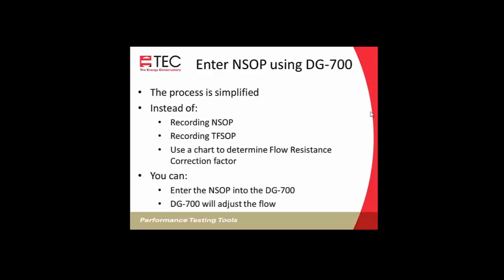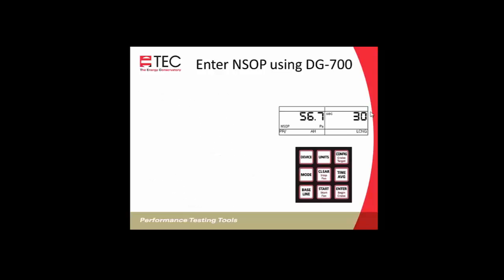similar to entering a baseline into the DG700. So those of you who do blower door tests are familiar with that baseline function of the gauge. So you'll enter in that normal system operating pressure, and then the DG700 will automatically adjust the flow for the difference between the normal system operating pressure and the true flow system operating pressure. So it really makes that whole process much simpler. So we'll connect the tubing from the probe to the gauge.